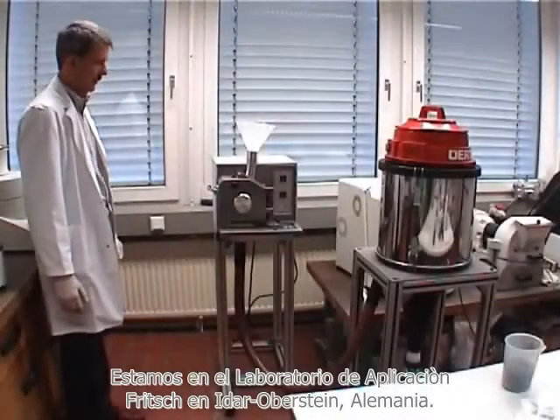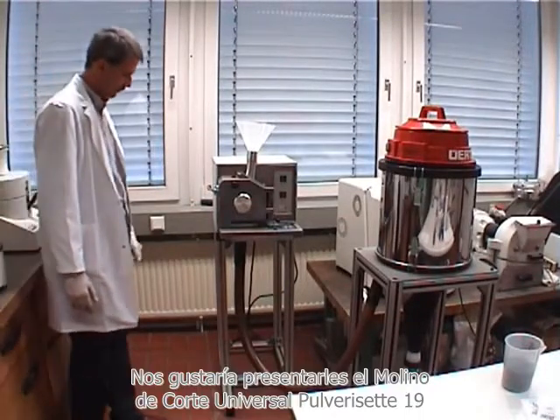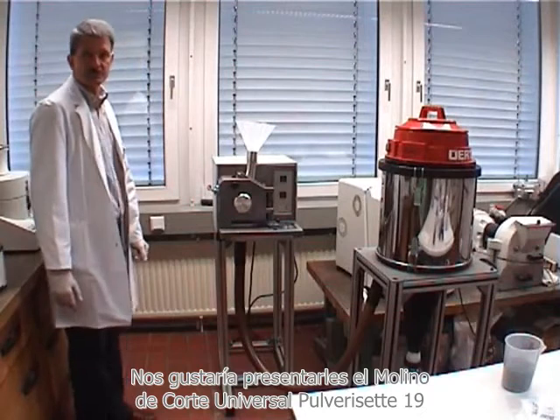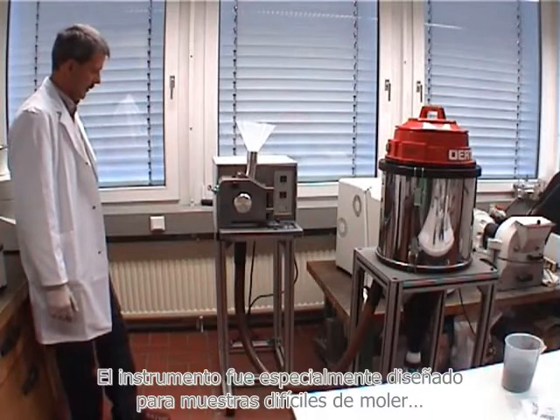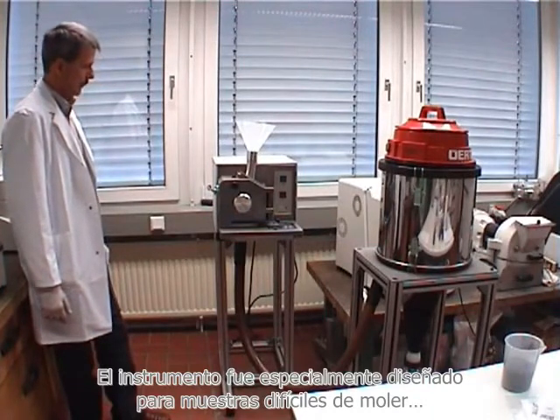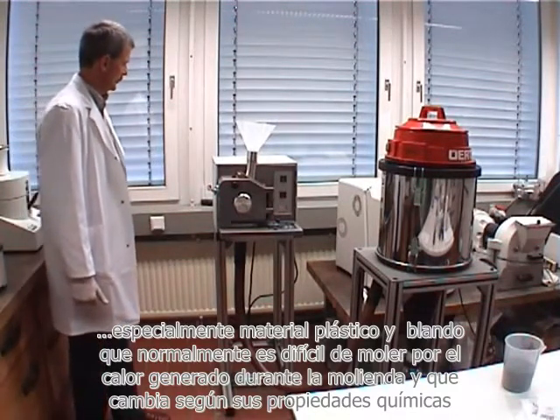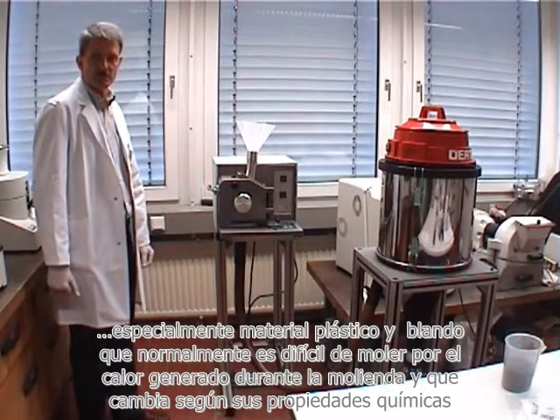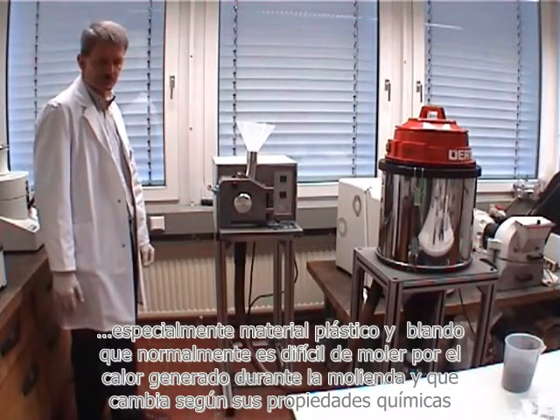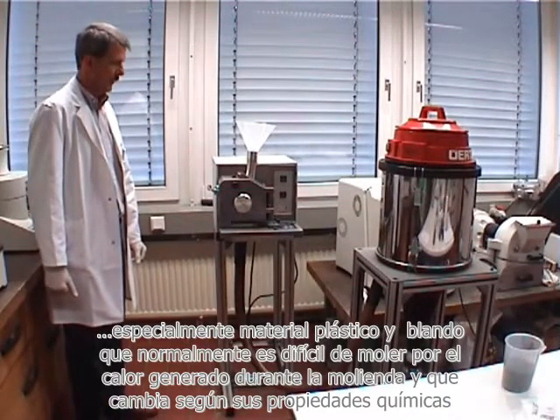We are in the Fritsch Application Laboratory in Idar-Oberstein in Germany. We would like to present you the Pulverisette 19 Universal Cutting Mill. That instrument was especially developed for difficult to grind samples, especially plastic materials and soft materials, which normally are difficult to grind because they heat up during the grinding and there may be changes in the chemical properties.